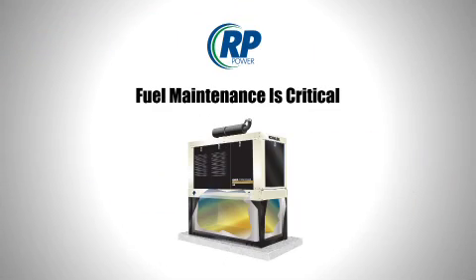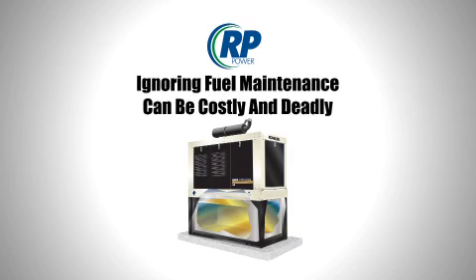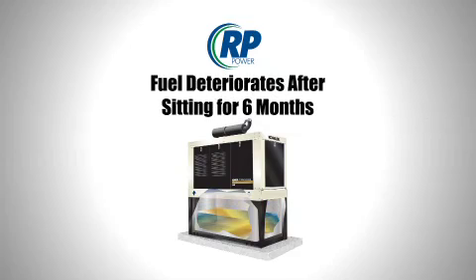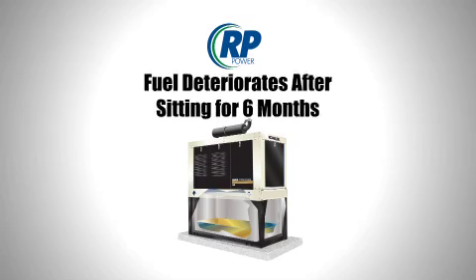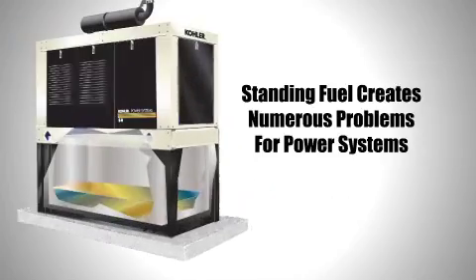One of the most common causes of failure and reduction in performance is insufficient attention paid to a system's diesel supply. Diesel left standing for extended periods degrades substantially to the point of becoming totally useless. Standby power systems are particularly susceptible to diesel fuel issues because their fuel source is left standing for several months.